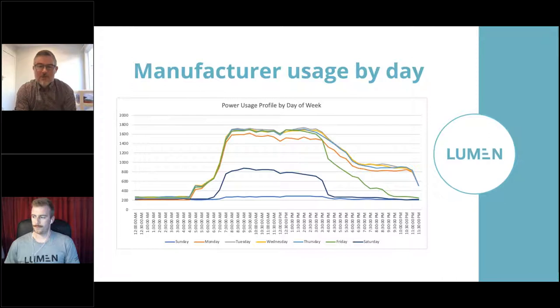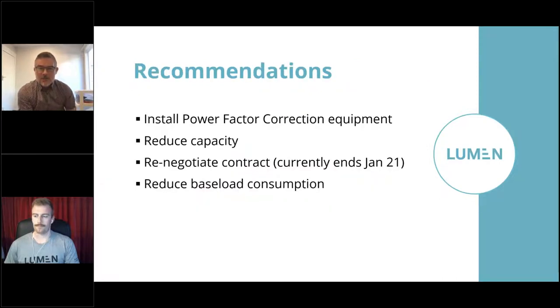The other thing we observe on this one, that there is a reasonable amount of baseload energy. So that's just constant energy that's being drawn from the network. And we want to understand why that's occurring and what we might be able to do to reduce that. So if we can reduce that baseload, that will apply 24/7, and we can get some pretty good energy savings out of that as well. So the recommendations on that one: installing power factor correction equipment, reducing the capacity.